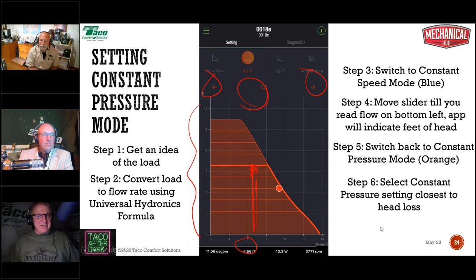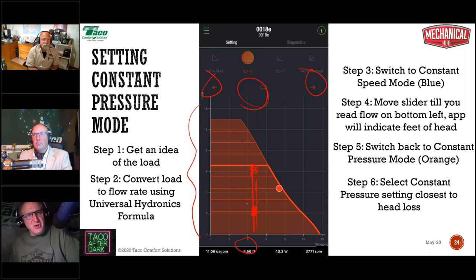So that's how simple it is to dial that in. Once you know the flow, go to the blue, it'll tell you the head. So if it was 7 gallons a minute and only 4 feet of head, I'd touch that line and I'm working down there. Again, about as well as a circulator can be programmed. That's the beauty of the app.